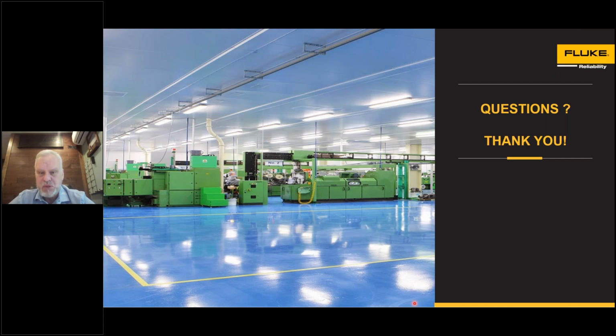So the belt and suspenders approach that we take is that any fault that becomes a serious, actionable fault gets pushed to a human analyst. One of my analyst team then reviews that and validates those results, because again, this may end up being a costly repair for you, the customer. And so we want to confirm those results and add any additional context that the human analyst might have. Analysts are very experienced and they understand a lot of the nuance here, particularly in certain industries such as food or metals, and then pass that result to you, the customer. So really, compared to that other approach, it just adds a lot of additional context.